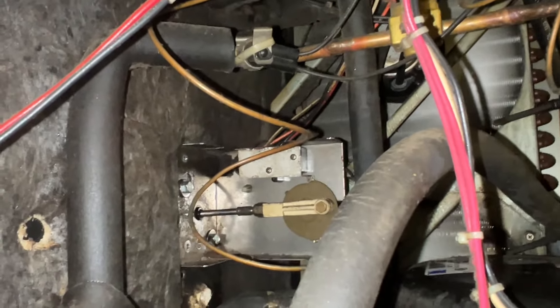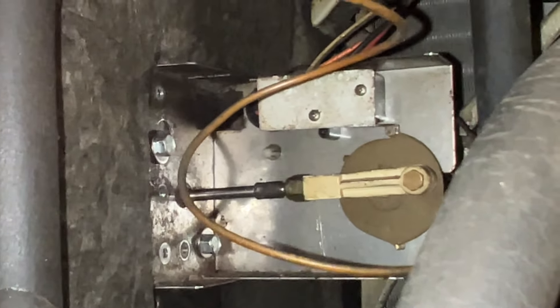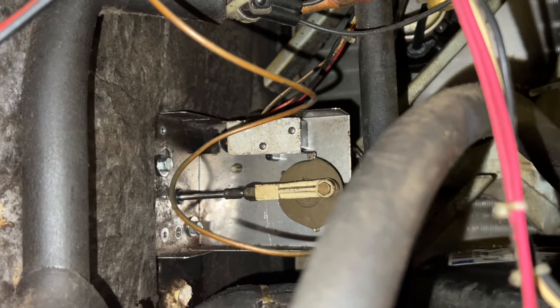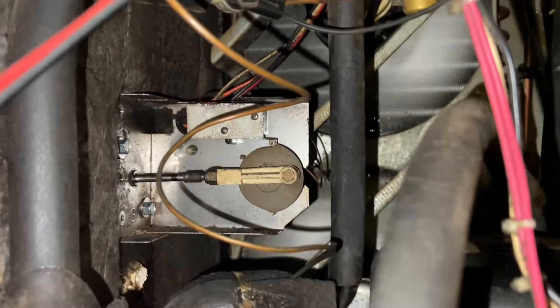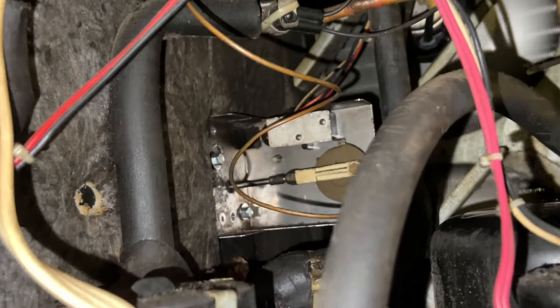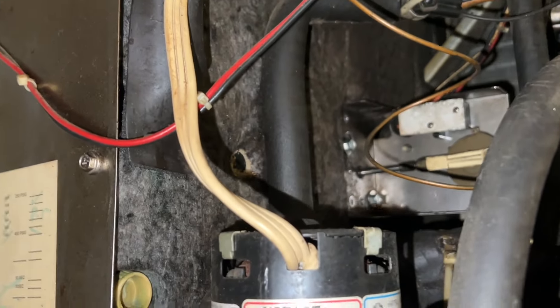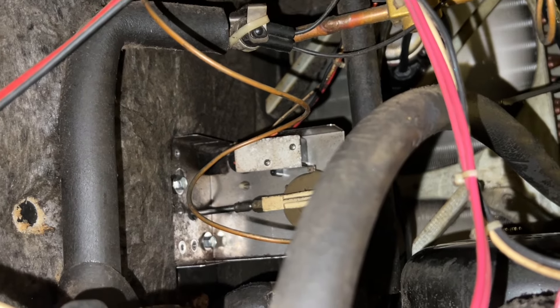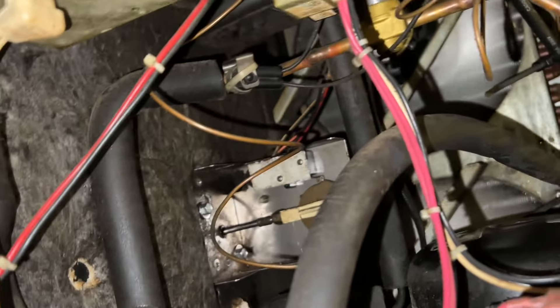It works. It's like a three-minute harvest — over three minutes, I think. This machine is done. The evaporator has got loose grids on it. It's too long a harvest, the evaporator's probably messed up, the tube's coming away from it, and it's got loose metal pieces. Yeah, this thing's done.